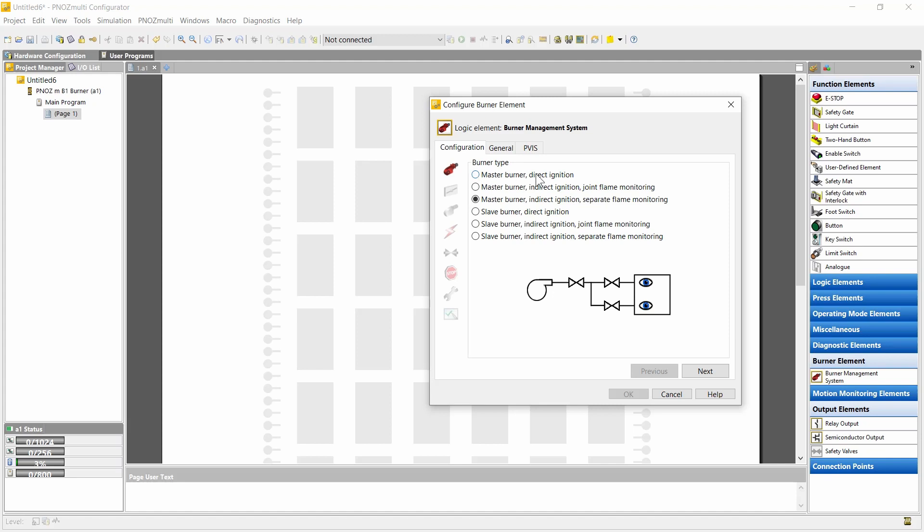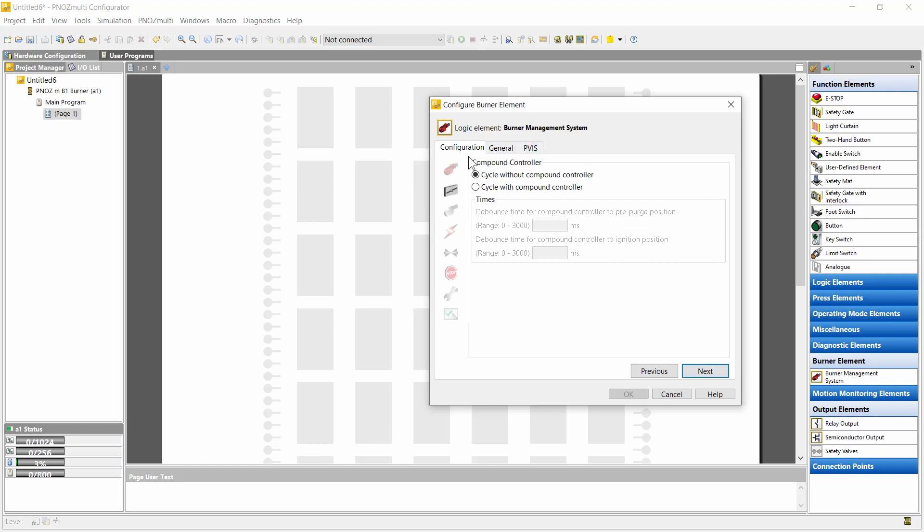Here we can select direct ignition, meaning without ignition burner, and indirect ignition, meaning with ignition burner. And there we can select joint flame monitoring or separate flame monitoring for main flame and ignition flame. The same we can configure for the slave burner. In this case we can configure the compound controller. The PNOZmulti does not include a compound controller but it can communicate and interface with an external compound controller. If we select this, signals for the external compound controller are available and included in the sequence.